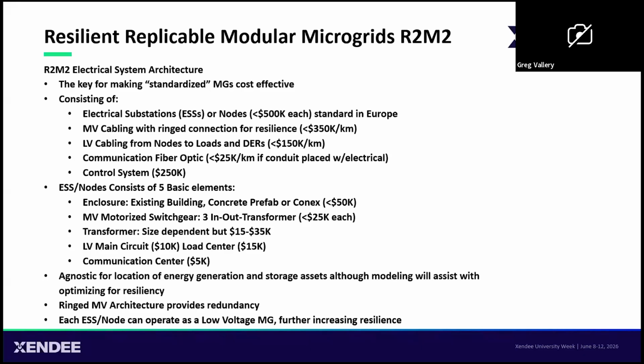So R2M2, what is it? We call it resilient, replicable, modular microgrids. We kind of coined that phrase or acronym out in California, but I really took it from what I had witnessed and seen at various installations here in Europe. It consists of substations that are very standardized, with the installations typically having medium voltage cabling that rings all of these substations together. Then all the loads, the low voltage loads, are fed off each one of these substations. To complete the microgrid, you obviously need the communications aspect and a control system.